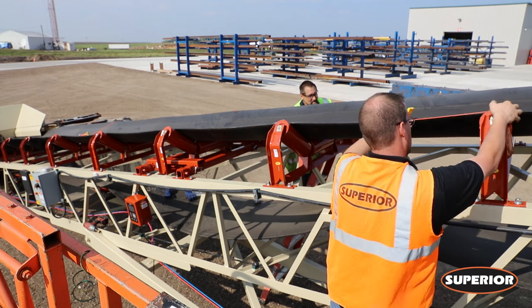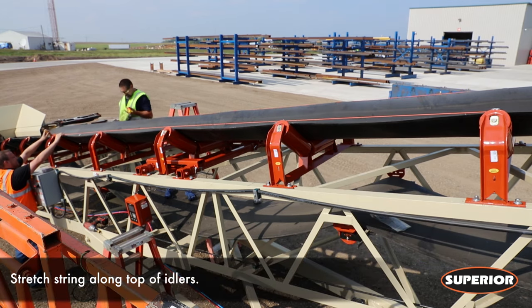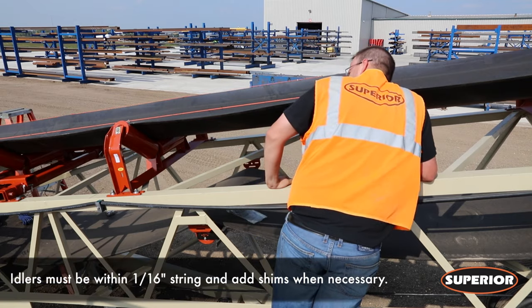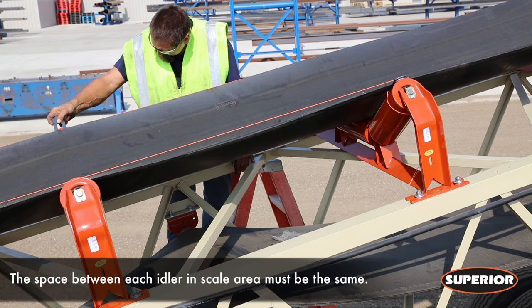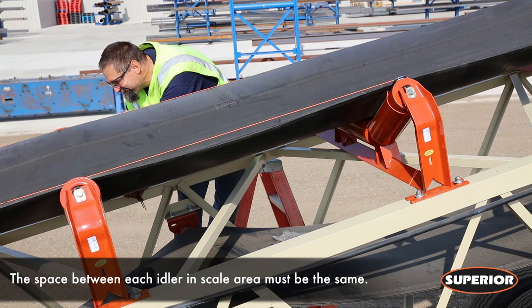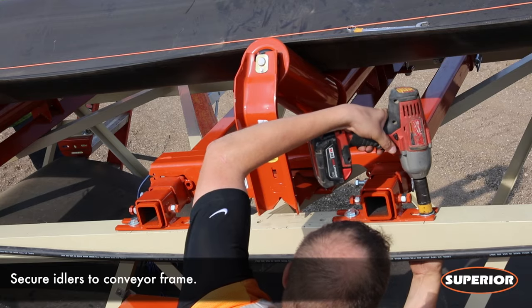You are now ready to perform a string test. This will ensure your scale and idlers are properly aligned. Stretch string over the top of idlers on both sides of the conveyor through the scale area. Align idlers within 1/16th of an inch of the string, adding shims as necessary. The space between each idler in the scale area needs to be the same or within 1/16th of an inch. Once properly aligned, completely secure idlers to the conveyor frame.